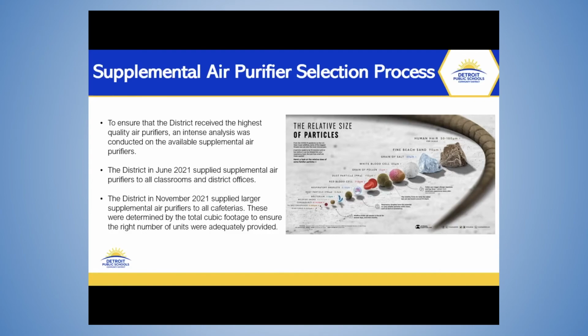We know that the COVID particle ranges anywhere from 0.06 microns to 1.4 microns. So we were looking at supplemental air purifiers that could filter down to 0.1, and those were the supplemental purifiers that had HEPA 13 filters. There's a difference between true HEPA and HEPA 13. True HEPA, for example, would only go down to 0.3 microns, whereas HEPA 13s will go down to 0.1 microns. So we wanted to capture, not necessarily the smallest COVID particle, but the mid-range to the large COVID particle size. That's why we selected air purifiers that could achieve those goals for us.